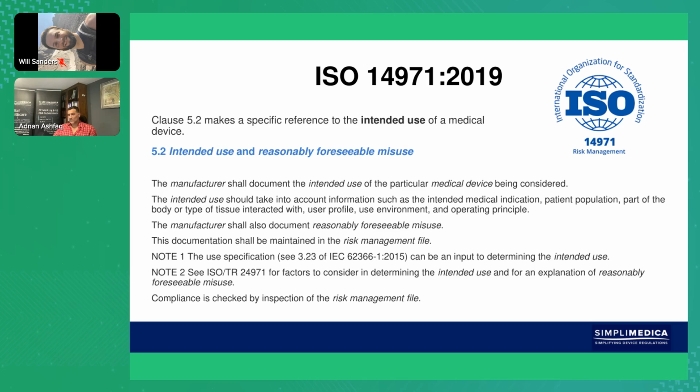So usability requirements, 62366. That's all about usability engineering, human factors. How is the device going to be used? So again, the intended use here is also very important. And then 24971, this is a tool that you can actually use to develop your intended use, because there's lots of questions that get asked in the Annex A of 24971, which will help you draft your intended purpose and make sure that you're on the right lines.